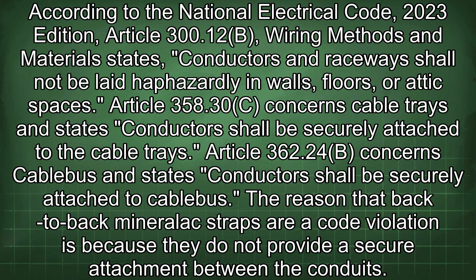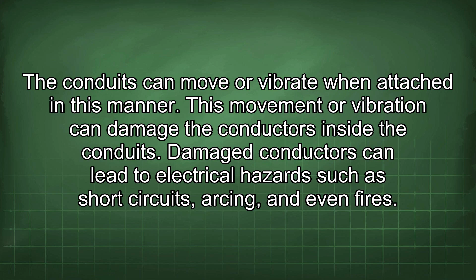The reason that back-to-back mineralac straps are a code violation is because they do not provide a secure attachment between the conduits. The conduits can move or vibrate when attached in this manner. This movement or vibration can damage the conductors inside the conduits. Damaged conductors can lead to electrical hazards such as short circuits, arcing, and even fires. Conductors and raceways must be securely attached to a solid surface to prevent movement and potential damage.